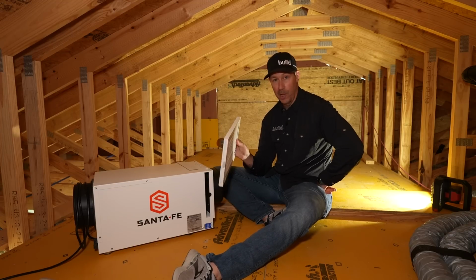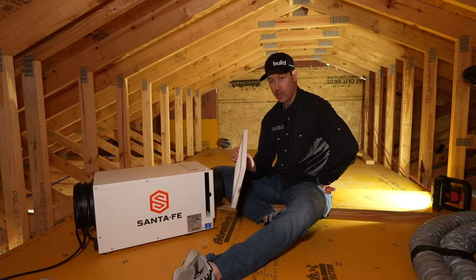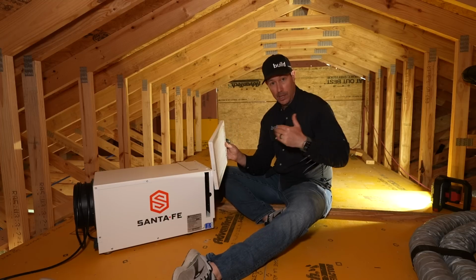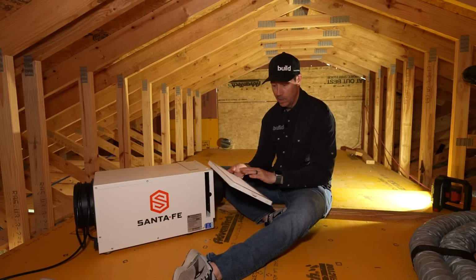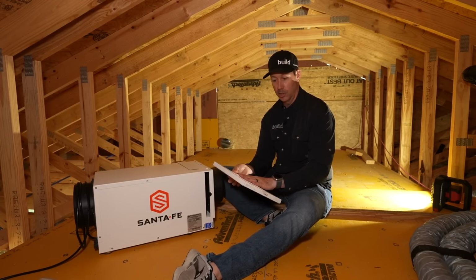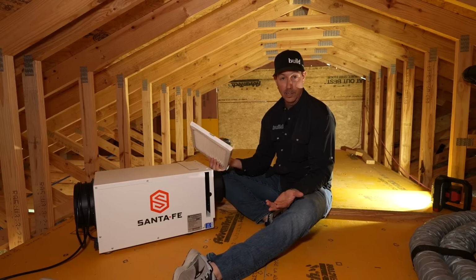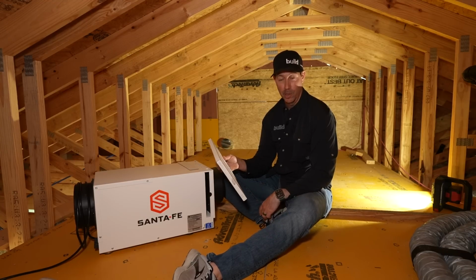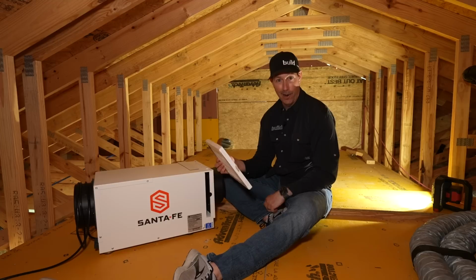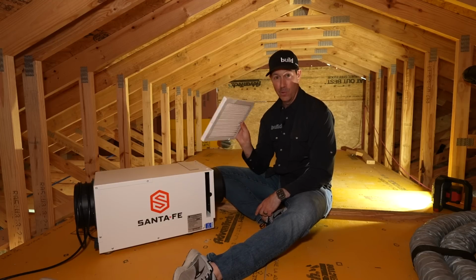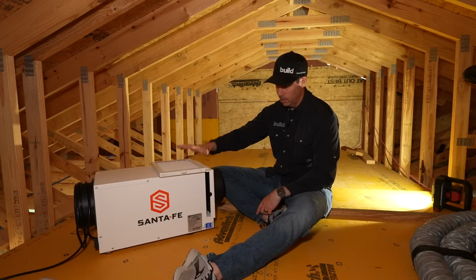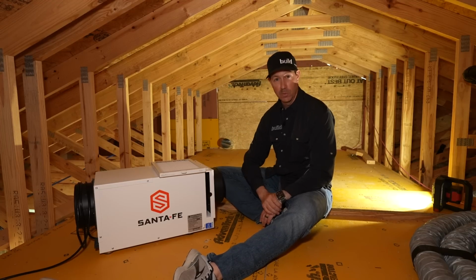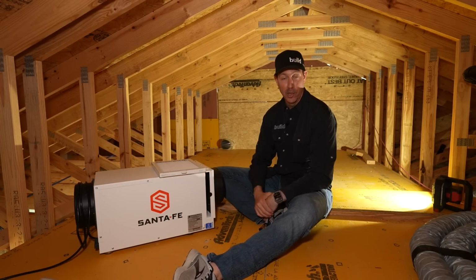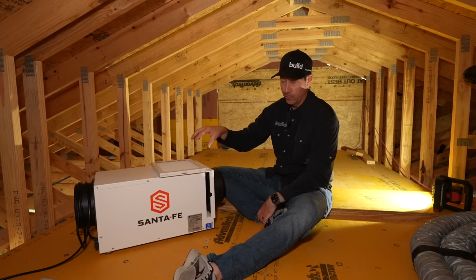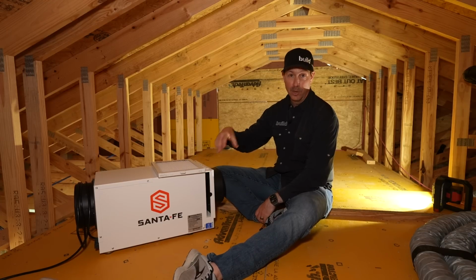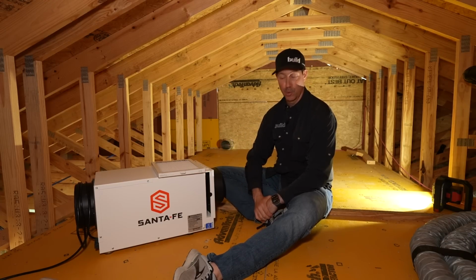I'll need to get up here about every 6 months to change this. Like all filters, when you take it out per the manufacturer specs, use a gauge to see how dirty it is and keep track, because I might not need to change it for more like 9 or 12 months. Every house and every air situation is a little different. When a manufacturer like Santa Fe recommends changing it every 6 months, that's really dependent on how dirty the air in your house is. If this had a fresh air input, it would get dirty much sooner, and I'd probably want to replace it every 3 months.